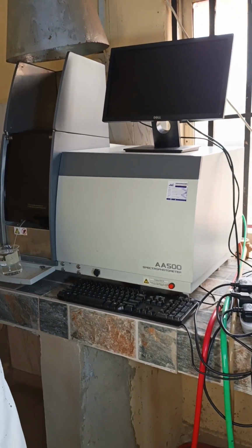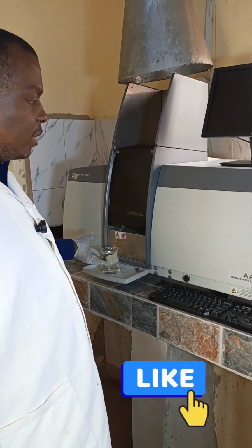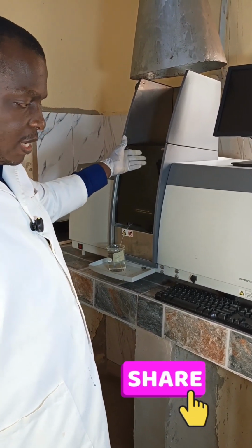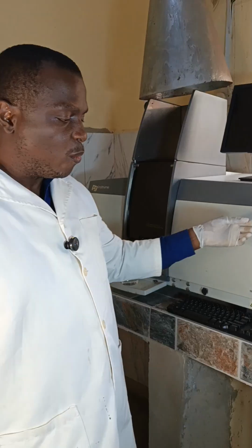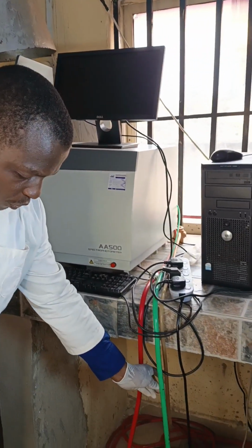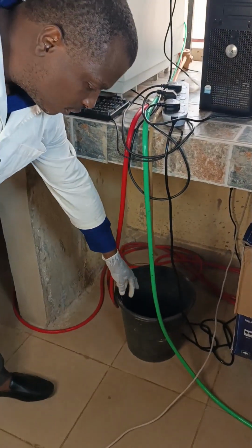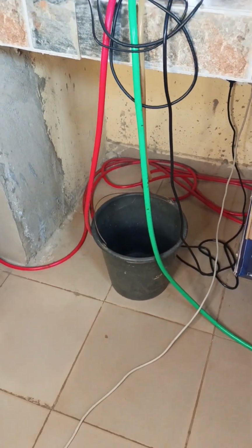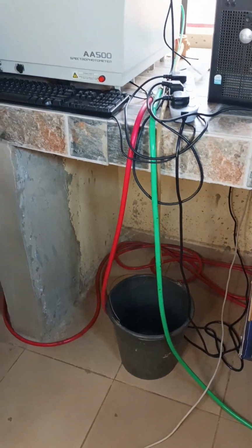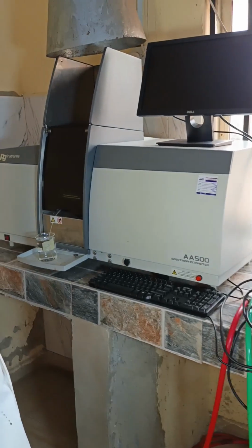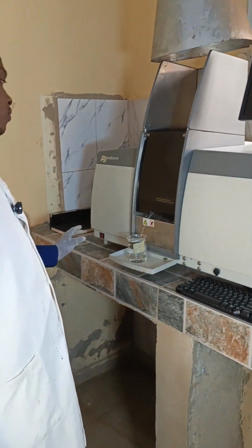Now, since the sample, which is liquid, is pneumatically sucked by the nebulizer into the flame, there will be waste. The waste drain comes through this pipe and gets dropped in this bucket as waste, which will be thrown away as time goes on.